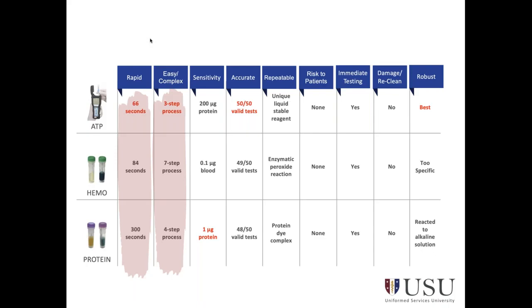Now with hemoglobin and protein, like I mentioned, because they're really small vials, about the size of the actual picture on your screen, maybe, depending how big your monitor is. But they're very small, and they come with a stand where you can put the ampules in while you do the testing and put the cotton swabs in and cut them and all that stuff. And that way you can just leave them in there. In the case of protein, then you have to wait the 5 minutes. You can label the time that you put it in, so you know exactly when. I did measure all this time with a digital timer, so I knew when to go back and check to see if it turned. Now I did have maybe one or two. It was two of them that at the 3:30 mark they turned positive. All the other ones turned almost immediately.